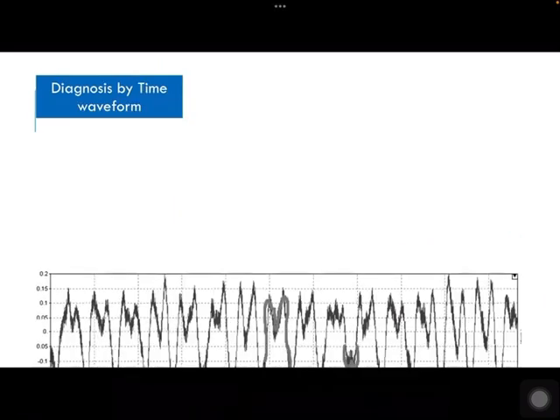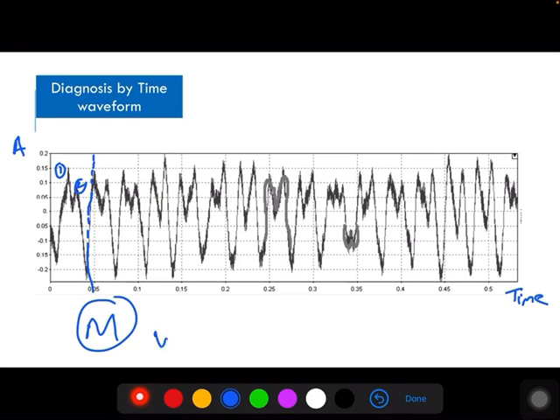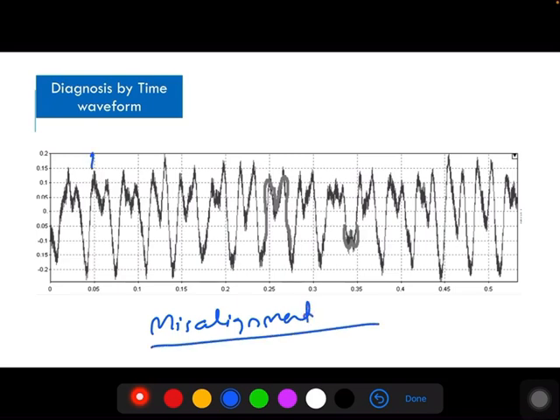Next, how to diagnose misalignment using the time waveform. Since equipment always has a combination of parallel and angular misalignment, you are generally getting one or two peaks in each revolution. In the time waveform — where time is the x-axis and amplitude is the y-axis — for each revolution you are getting two peaks. This pattern generally forms an M shape, or sometimes a W shape. If you are getting this type of time waveform with two peaks in every revolution, then the machine is in a misalignment condition.